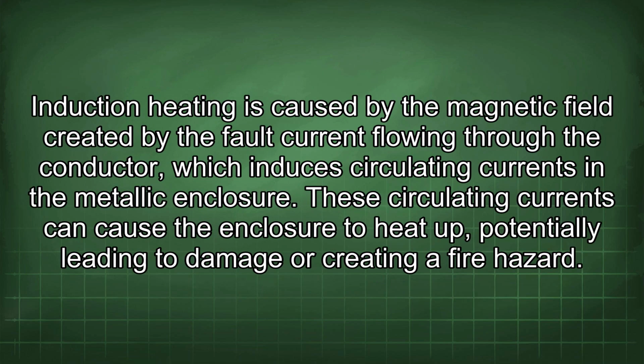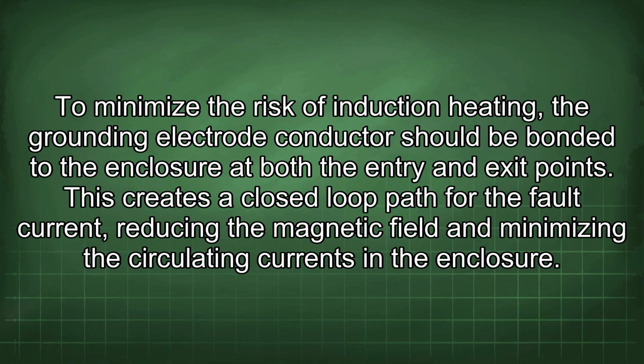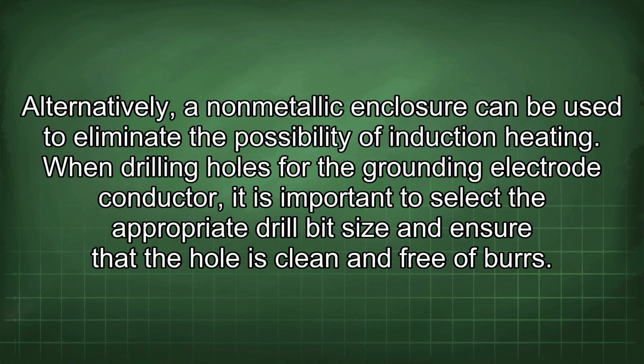Induction heating is caused by the magnetic fields created by the fault current flowing through the conductor, which induces circulating currents in the metallic enclosure. These circulating currents can cause the enclosure to heat up, potentially leading to damage or creating a fire hazard. To minimize the risk of induction heating, the grounding electrode conductor should be bonded to the enclosure at both the entry and exit points. This creates a closed-loop path for the fault current, reducing the magnetic field and minimizing the circulating currents in the enclosure. Alternatively, a non-metallic enclosure can be used to eliminate the possibility of induction heating.